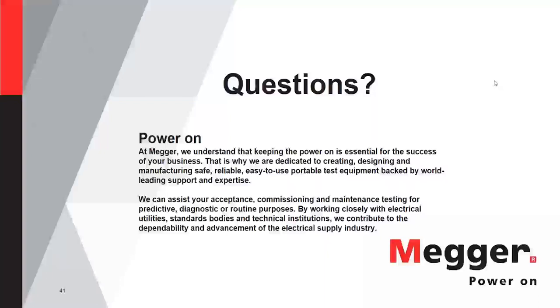So when you look at your percentage of change from baseline, like I said, with a flooded lead acid, 50 to 100% is good. But when you start getting to a VRLA, you might want to consider being a little bit more cautious if it's in a critical application and saying 20 to 30%. So I hope that answers that somewhat. Okay. Thank you, Andy. All right, on to the next question.